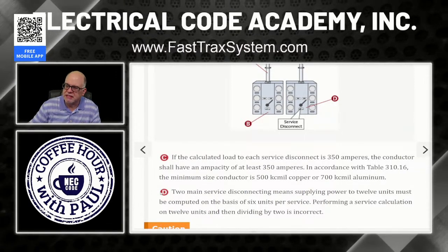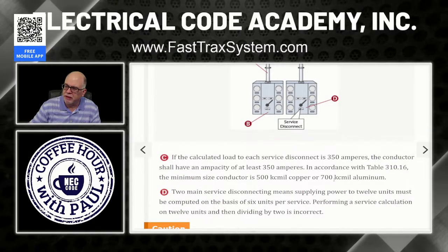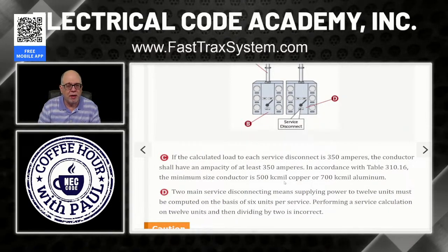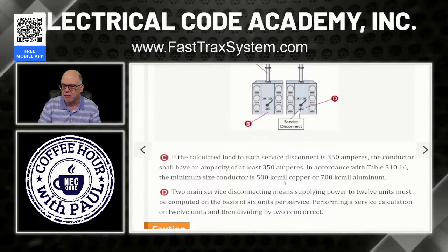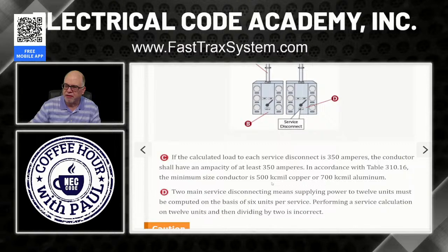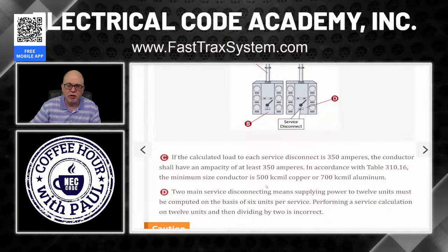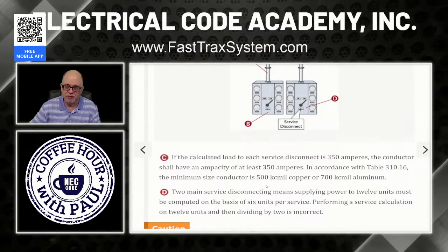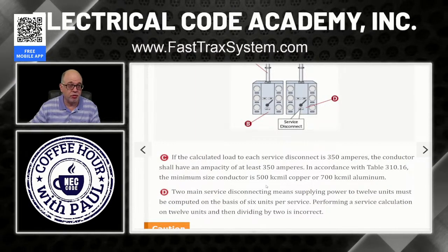In accordance with 310.16, the minimum size conductor is a 500 kcmil copper or a 700 kcmil aluminum. Now, a 500 kcmil copper, on an exam, y'all know by now, you always assume copper unless stated otherwise. If they ask you for aluminum, then you use aluminum. But if they don't state aluminum, always use copper. In this case, a 500 kcmil copper under the 75 degree terminals, which is probably what everything's going to be rated at, gives you 380 amperes. Well, obviously a 380 ampere conductor can easily handle 350 amps of calculated load, and the overcurrent protective device is more than capable of protecting a conductor that's good for 380 amps.